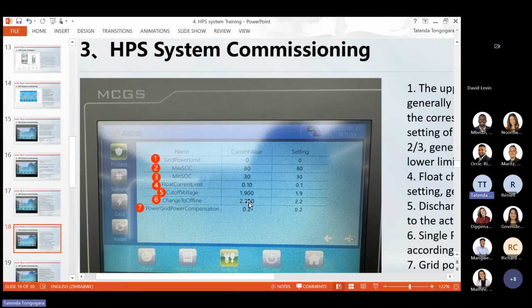So change to offline for most batteries is around 3.3, 3.4, but each and every battery has got its own value. So if you're not sure, contact us, contact your battery manufacturer. If you cannot get hold of them, contact us, give us your nameplate. We calculate these values for you.